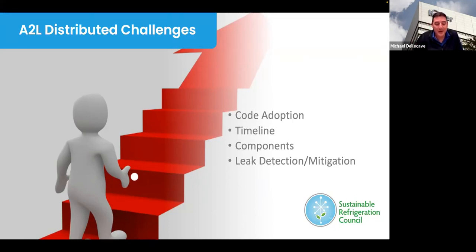Again, I mentioned components. It is a bonus that they are very similar to what we do today, but while they're similar, they do need to be rated for A2L. So you can't just take an A2L and put it into a component that is using a refrigerant today. And I'd like to make a point here that just like with CO2 or R290, an A2L cannot just be put into an existing system. All components, including your cases and piping, will most likely not work. All of that equipment will have to be changed out when moving to these new refrigerants and new architectures.